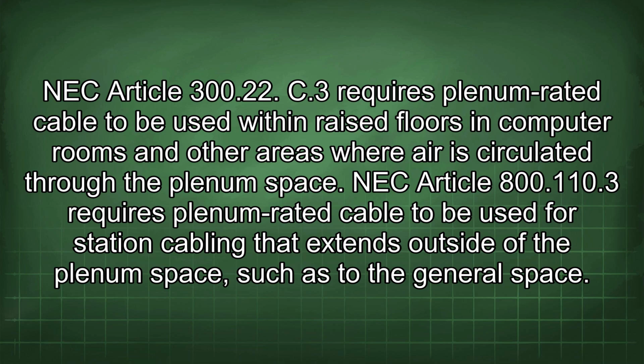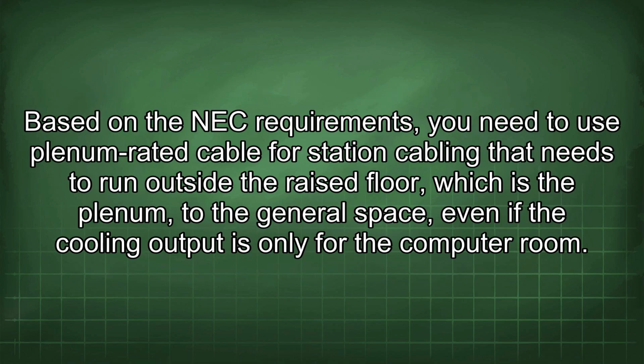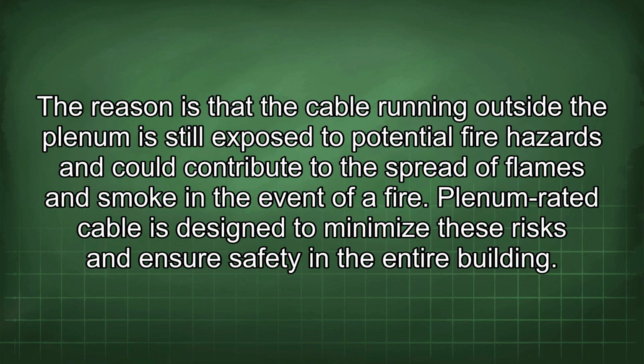NEC Article 800.110 requires plenum-rated cable to be used for station cabling that extends outside of the plenum space, such as to the general space. Based on the NEC requirements, you need to use plenum-rated cable for station cabling that needs to run outside the raised floor, which is the plenum, to the general space, even if the cooling output is only for the computer room. The reason is that the cable running outside the plenum is still exposed to potential fire hazards and could contribute to the spread of flames and smoke in the event of a fire. Plenum-rated cable is designed to minimize these risks and ensure safety in the entire building.